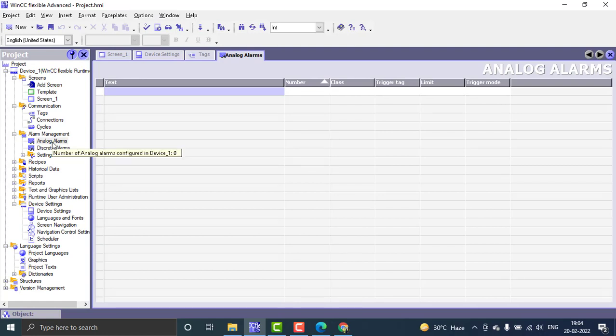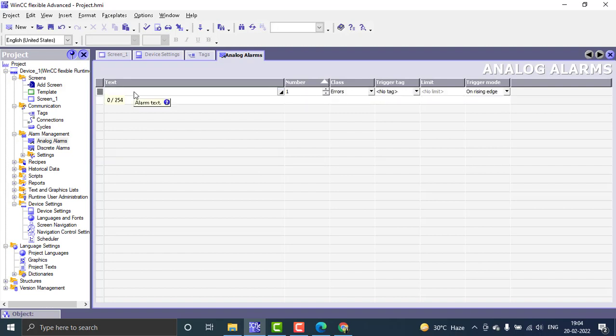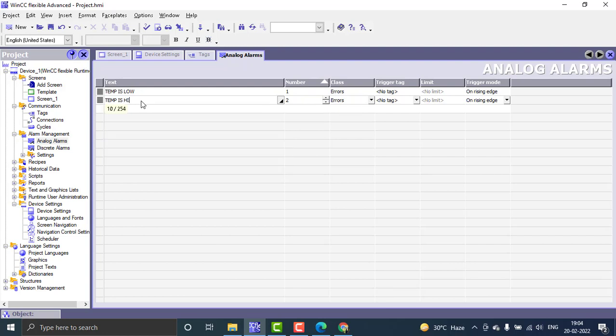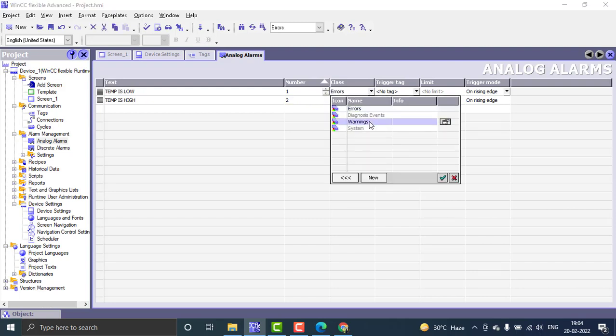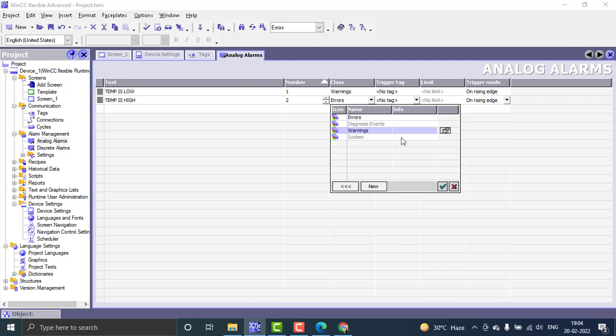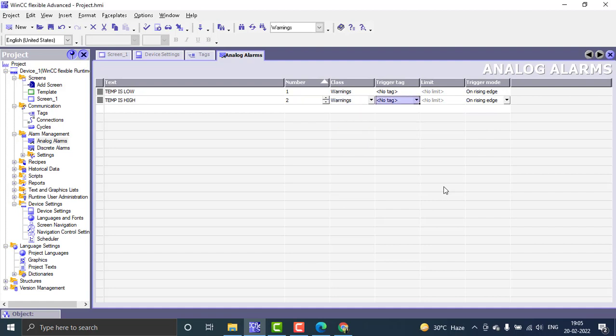Next, I have to create the alarm using that tag. When the temperature goes above a specific value, we create an alarm. The first alarm text is 'temp is low' and the second is 'temp is high' — alarm number two and one. The class for both will be 'warning'. You can also set it to 'error' or create a user-defined class like 'critical'.